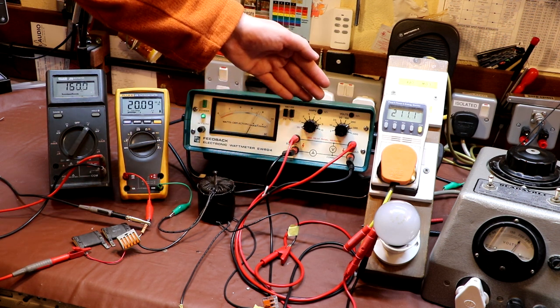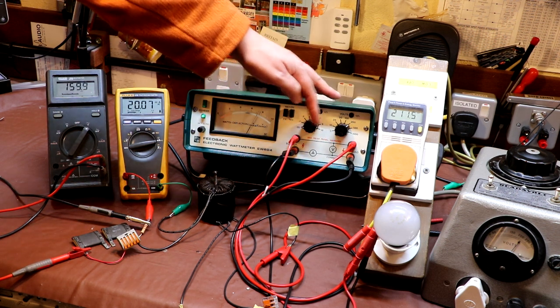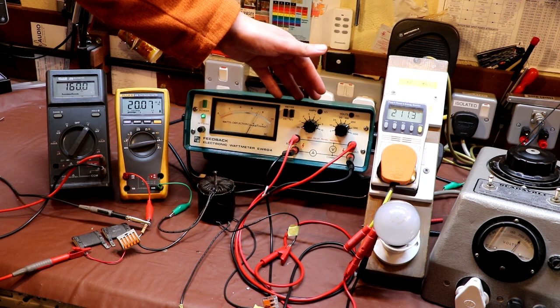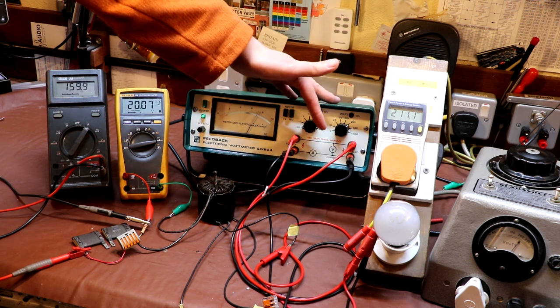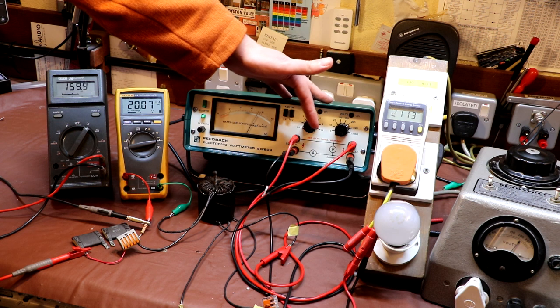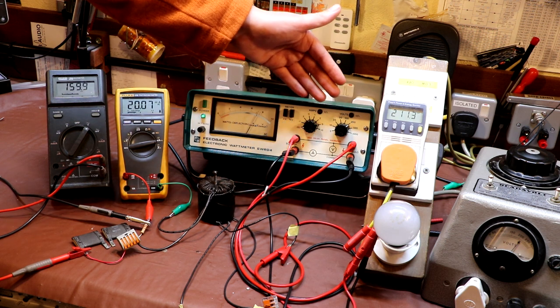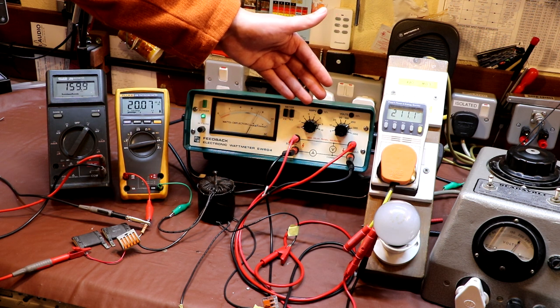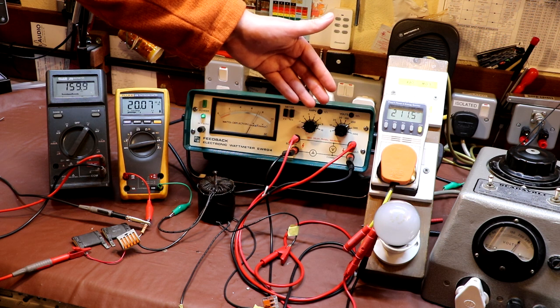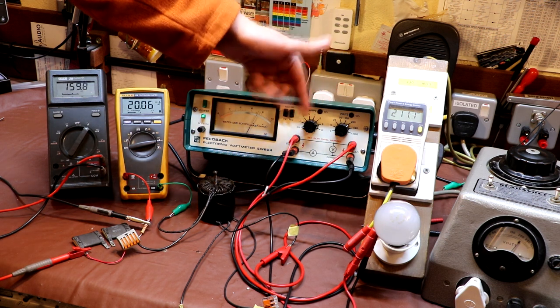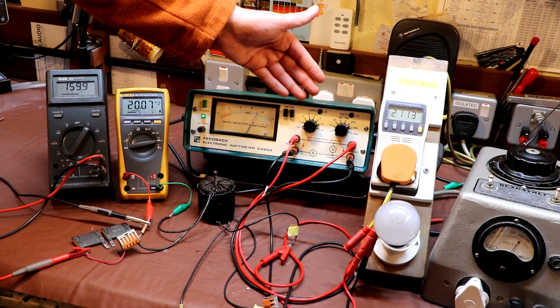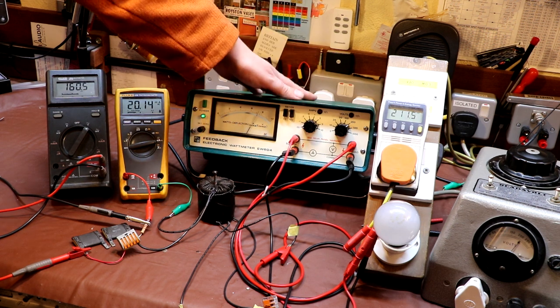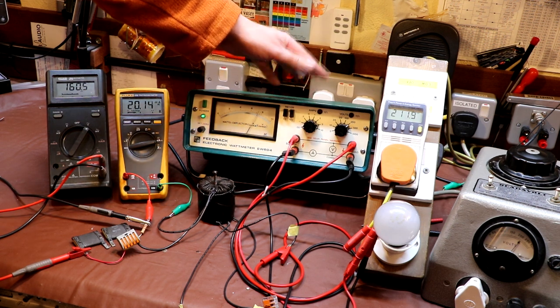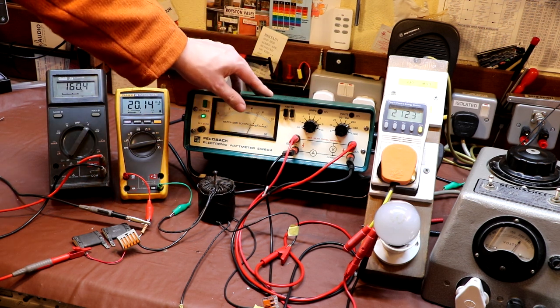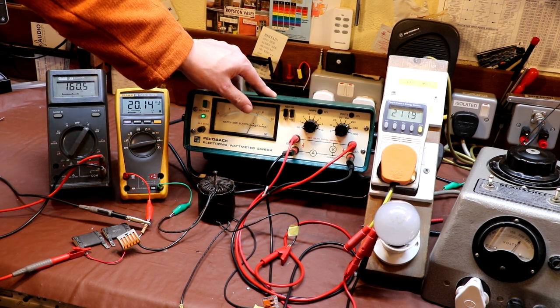Now if you were to do the calculation manually and measure the voltage and the current using separate meters, you'd also have to measure the phase angle between the voltage and the current, and the phase angle is how much the voltage and current are out of phase with each other. So if you know the phase angle, you know the voltage and you know the current, you can then calculate what the true power is. But this meter does all that clever maths internally, and just displays a meter reading here which is showing true power.